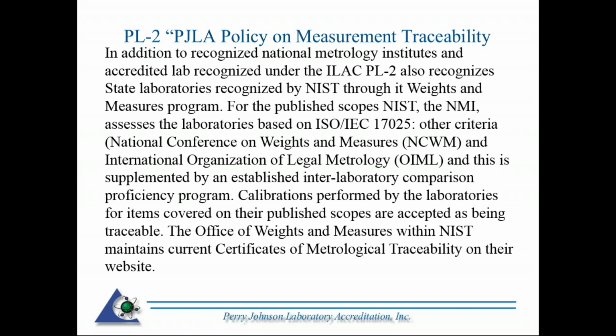All right, we're going to look at PL2 now. The things we've already discussed in the requirements of 17025 and the annex at the end of the 2017 standard are covered under PL2. There are a couple of other things I want to expand on that are also covered under PL2. In addition to recognizing NMIs and accredited labs under ILAC, Perry Johnson under PL2 also recognizes state laboratories recognized by NIST through its Weights and Measures program. That's the NIST Office of Weights and Measures, which has a program amongst the state metrology labs in order to achieve a certificate of traceability.